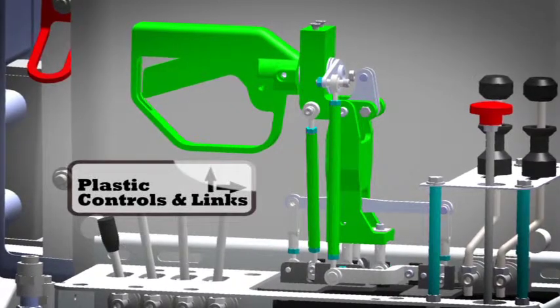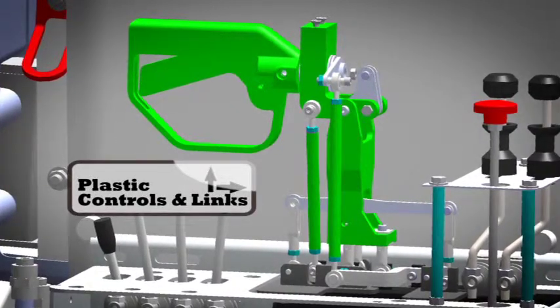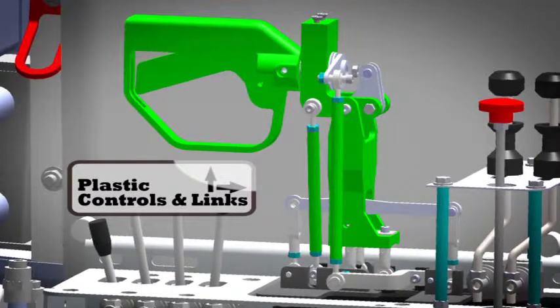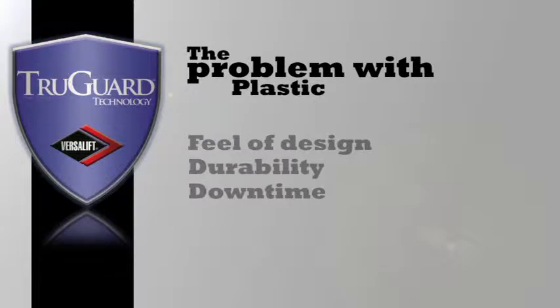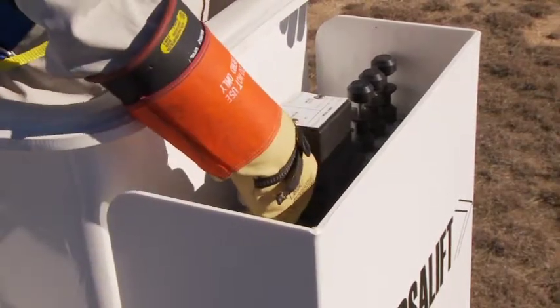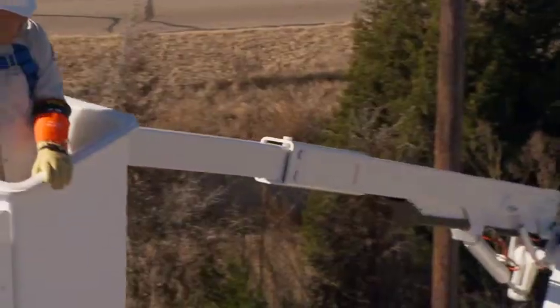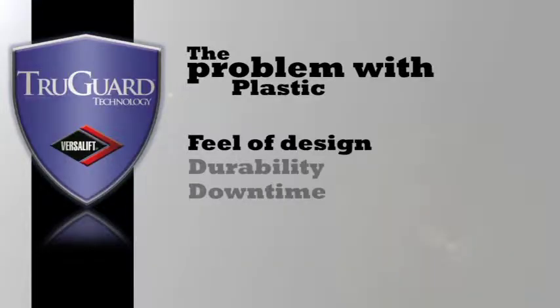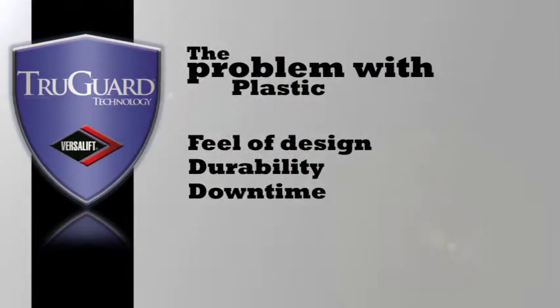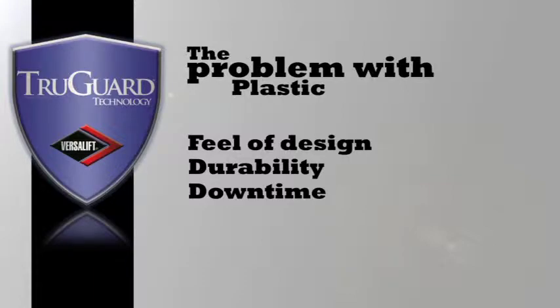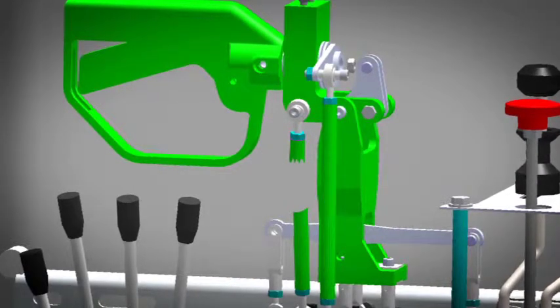All plastic handle controls are designed with the same basically plastic elements, linkage or handles. You have three problems with these. The first one is the feel of the design. The operators just don't get the same feel they get with a metal handle control. They just don't get the reaction they're used to. The second one is the durability of the unit. Plastic wears and tears and it stretches. And once again, the operators prefer a more robust metal design. The third element is the downtime. Since these are dielectrically tested, if one of the plastic linkages break, the unit should be taken out of service and returned to the shop for repair, thus adding downtime for the operator.